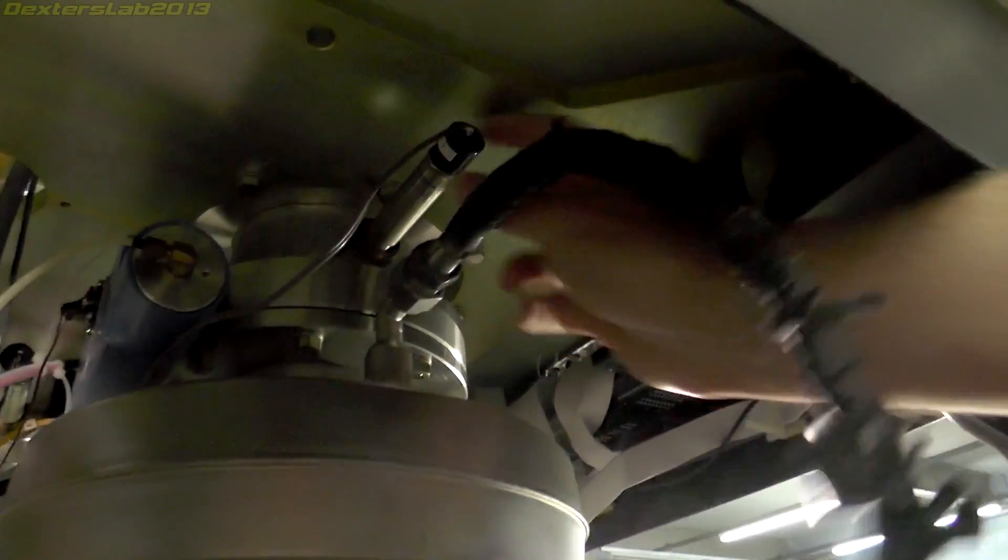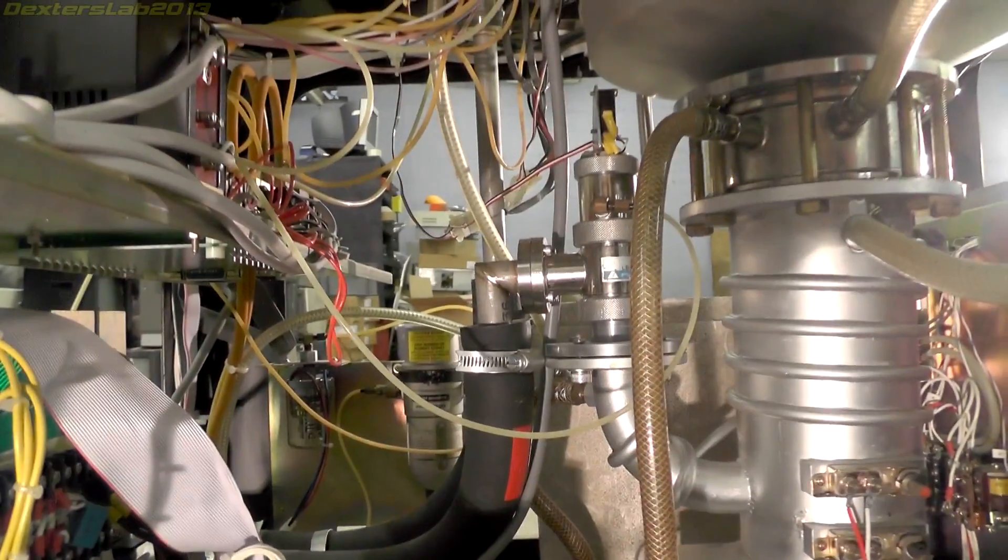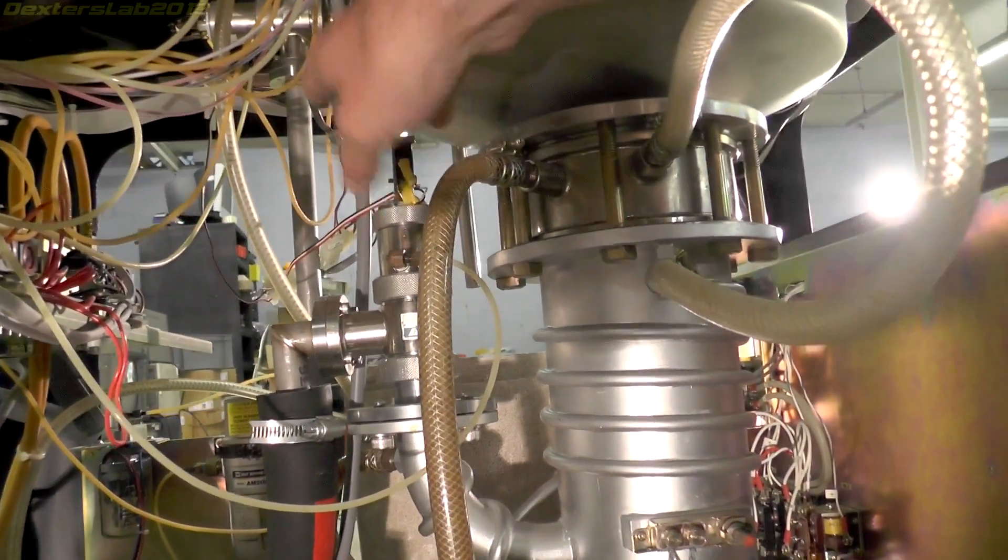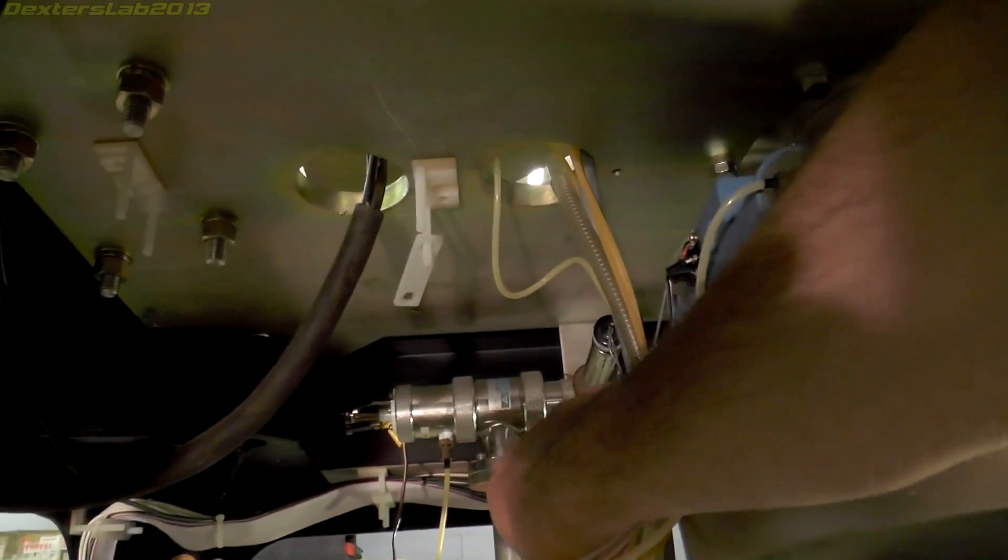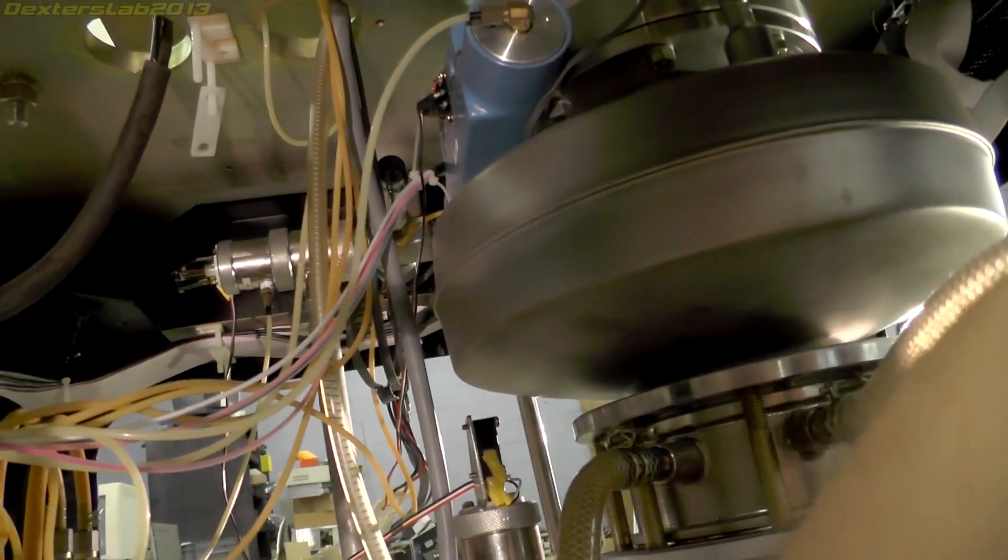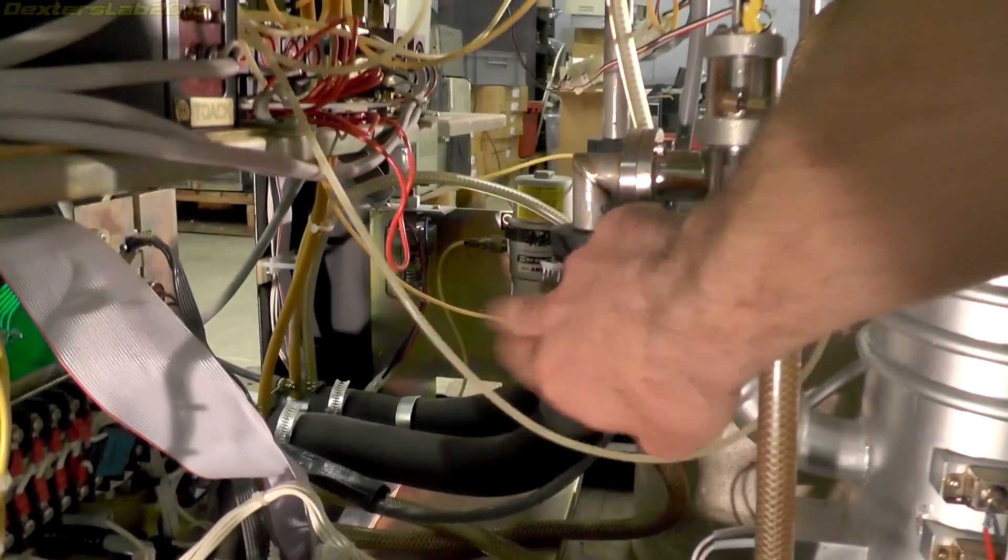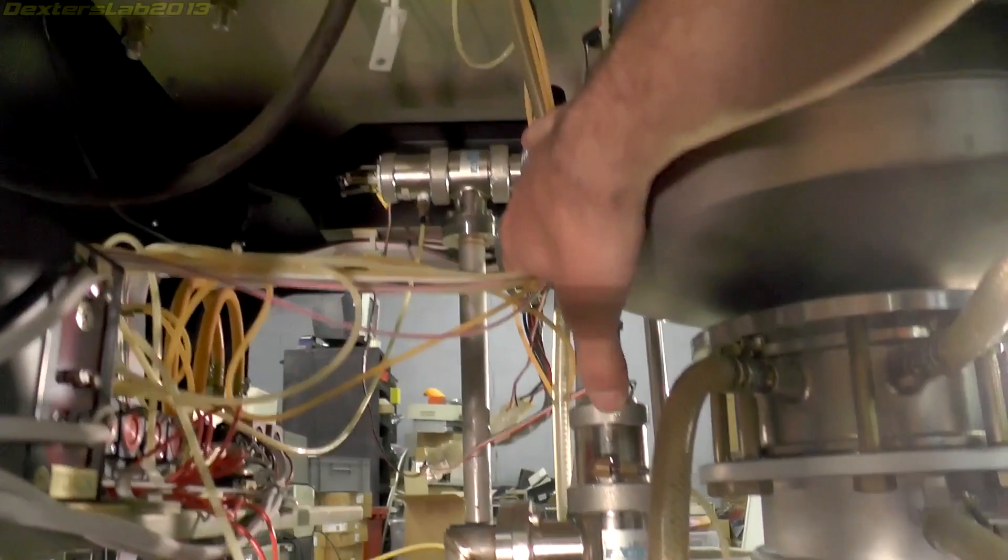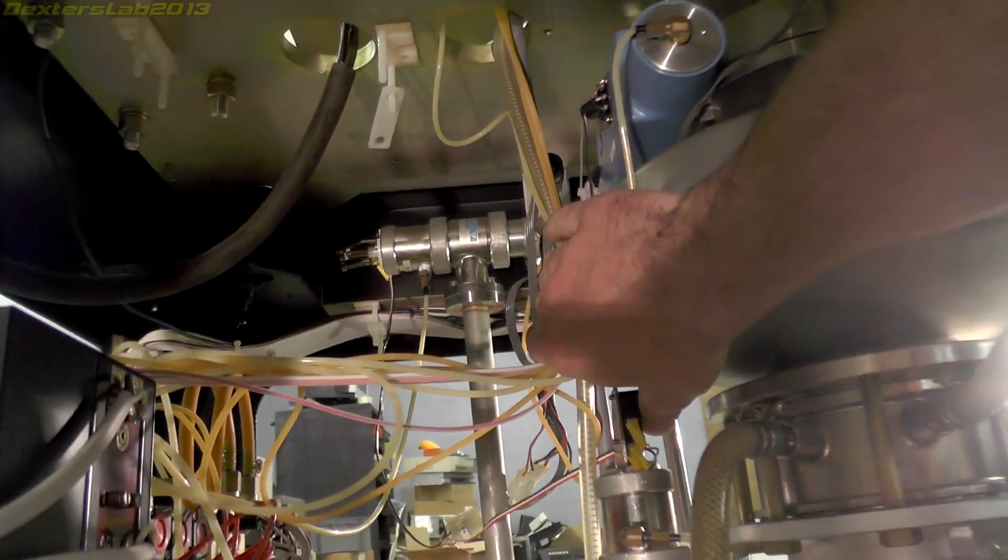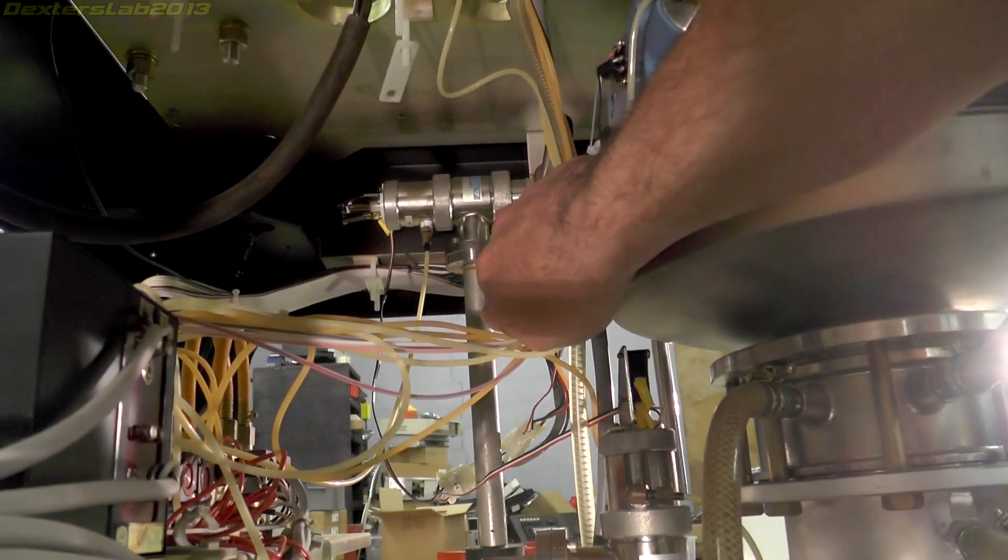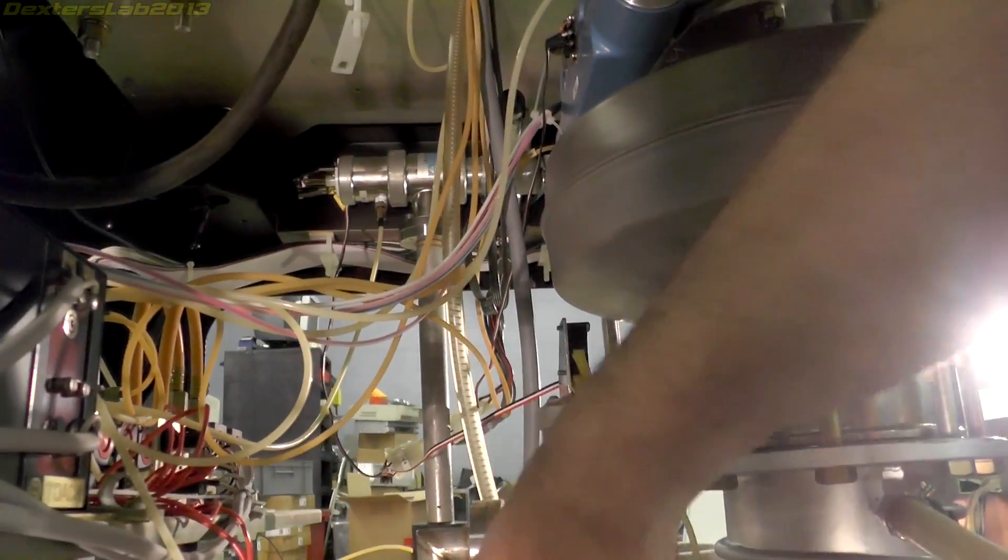There's random pipes all over this place, and I'm not entirely sure what they're for. There's a number of gauges. I think that's a Pirani gauge just up here. This looks like it's some kind of switching valve. There's also a small micro switch attached to the top of it. Over in the back there, these bits here, this is part of the sample exchange chamber vacuum system. So there's two pipes that run out to the back here. I think the actual main console, the control console, would have had at least one roughing pump, possibly two. So I think what they used was a roughing pump for the main chamber and then possibly a separate one for the sample exchange chamber. I don't believe the sample exchange chamber is brought down to full vacuum apart from when the airlock door is open. I think it's just brought down to a moderate low pressure, so I think there might be a separate feed off there to another roughing pump.